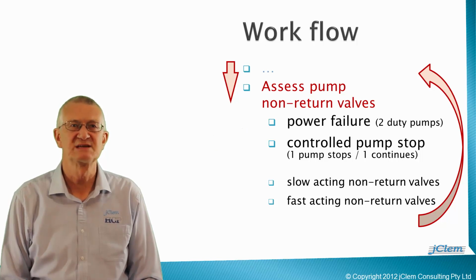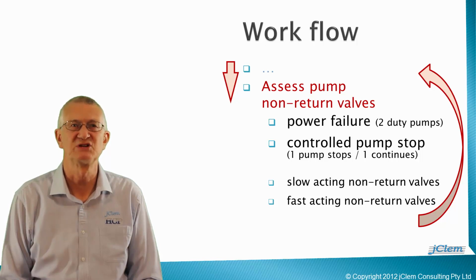These will be good skills to have if you ever work on a very large pumping station where the capital cost of appropriate or inappropriate non-return valves can be significant. It pays to do the required transient analyses well before the project budget becomes fixed and final.